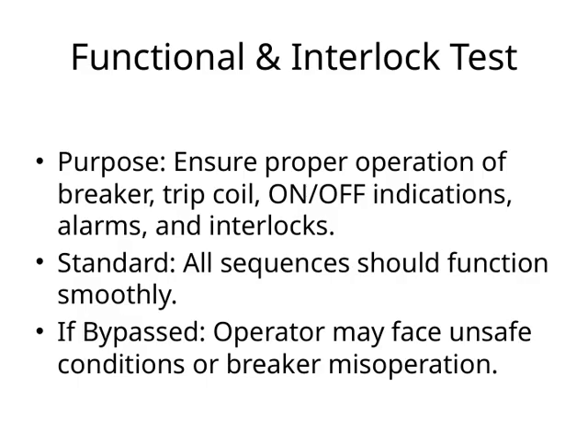If the system is bypassed, however, that can lead to serious issues. For example, the operator might face unsafe conditions or the breaker could misoperate. That's why proper testing and adherence to procedures are so critical. Remember, this test isn't just about verifying components. It's about ensuring the entire system's integrity and safety. When everything functions correctly, it helps us prevent accidents and maintain stable operations.